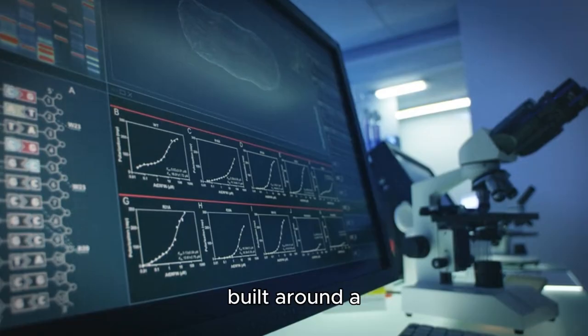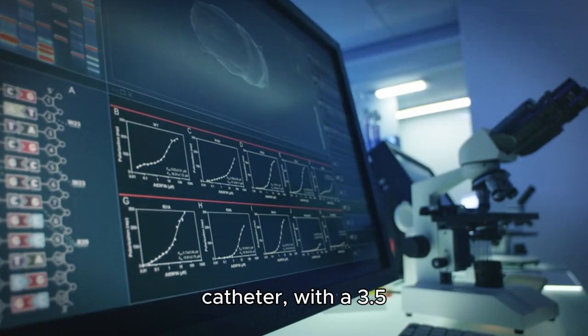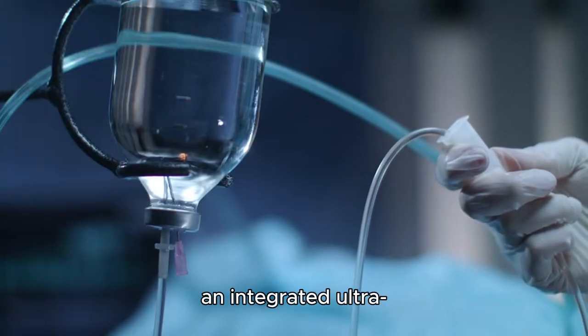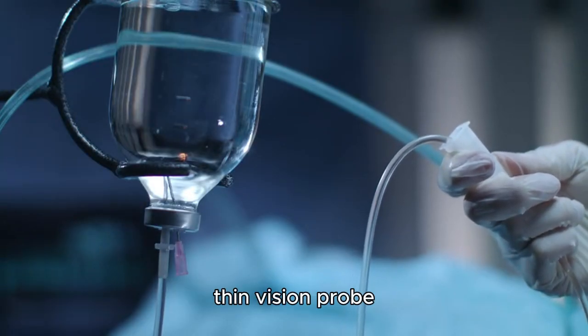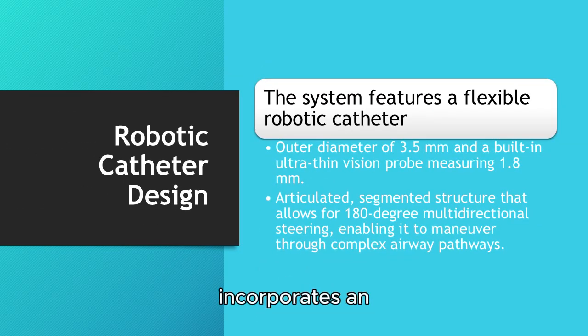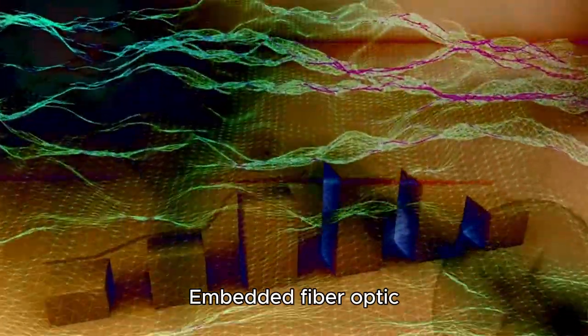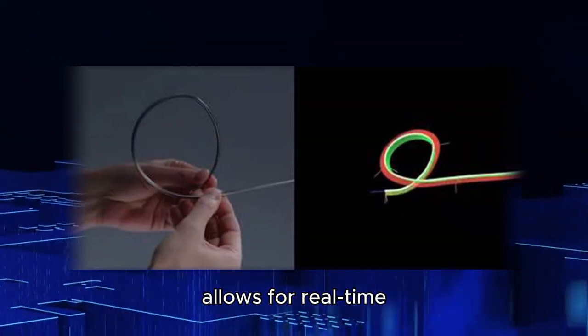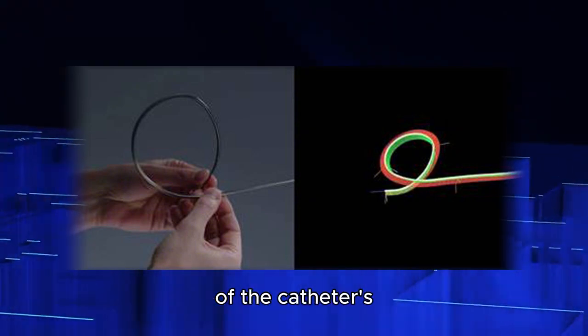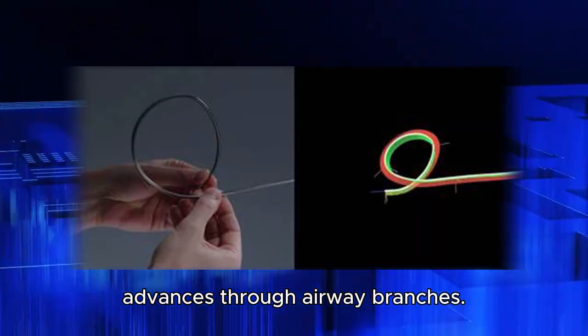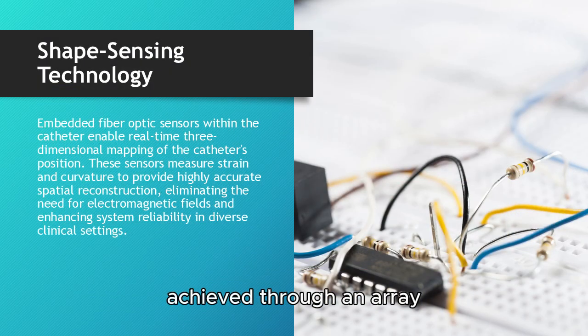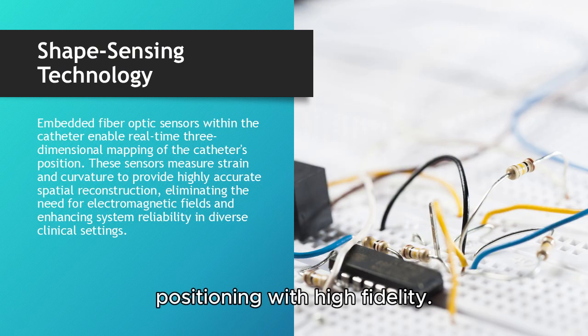The Ion system is built around a flexible robotic catheter, with a 3.5 mm outer diameter and an integrated ultra-thin vision probe measuring 1.8 mm. The catheter incorporates an articulated, segmented mechanical structure capable of multi-directional steering with a 180-degree articulation range. Embedded fiber optic shape sensing technology allows for real-time, three-dimensional mapping of the catheter's configuration as it advances through airway branches. This shape sensing is achieved through an array of optical fibers embedded along the catheter, measuring strain and curvature to reconstruct spatial positioning with high fidelity.